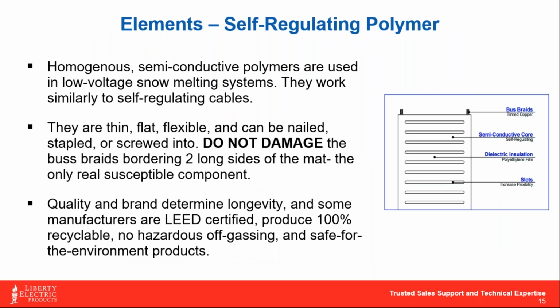Moving on, we're going to look at the self-regulating polymers. This product hasn't really hit the mainstream, but it's been around for 15 to 20 years. We started getting into it because it can be powered through a low voltage system, DC power, low voltage transformers. The self-regulating polymer works just like the self-regulating cable we talked about, expanding and contracting based on the surface temperature of what it's up against.